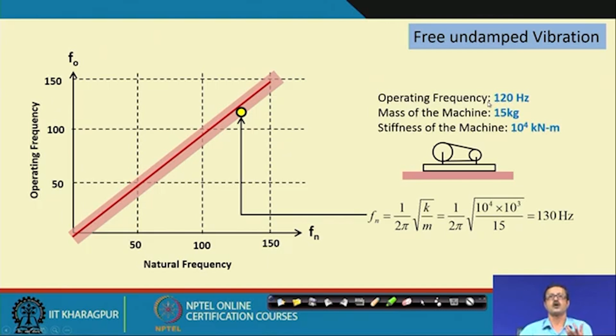So, I need to shift the natural frequency. What I did is I changed the mass of the machine, which was 15 kg and rested on the slab itself. Now I put a heavy mount system, and the mass is now, suppose, 60 kg. If it is 60 kg and the stiffness remains unchanged, the natural frequency becomes 65 hertz. So, the 130 hertz has moved to 65 hertz, and the operating frequency remains unchanged at 120, and this is your 65.